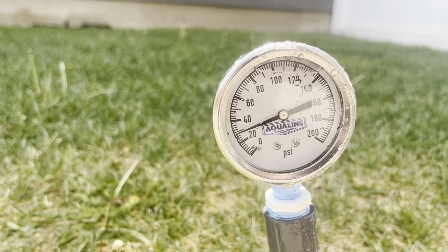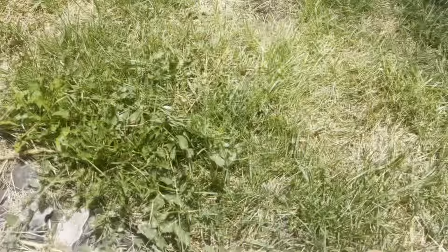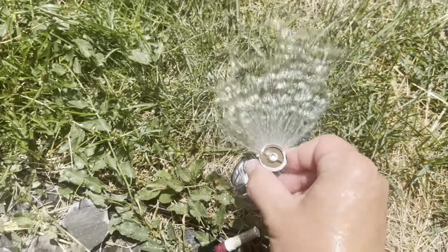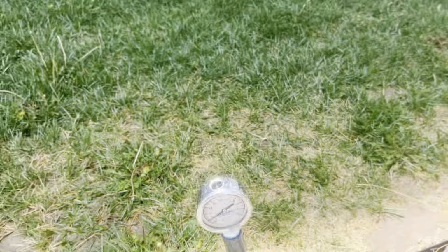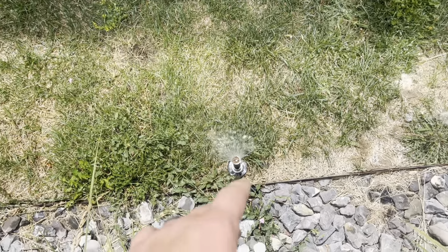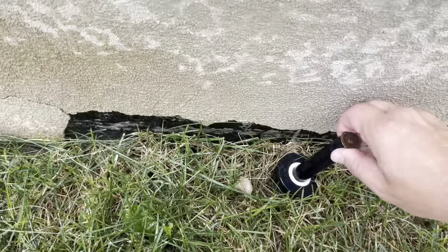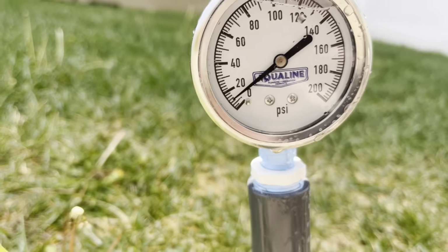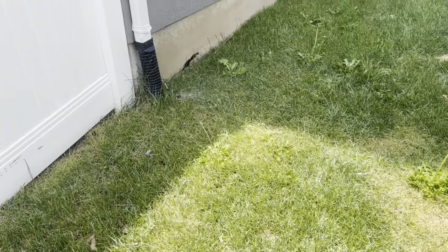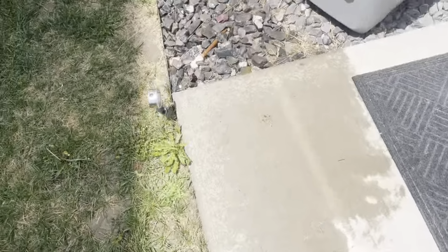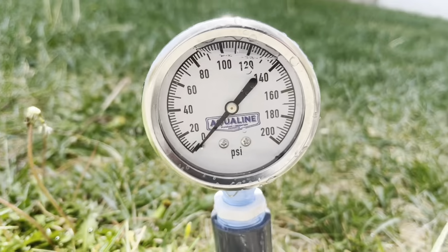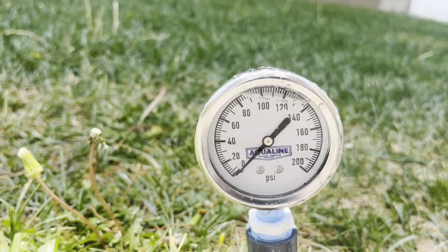That one only took us down by maybe 12, and we're up to like 28, 29. Let's go over and do this guy as well, and I'll open it so that it's not actually hitting me at the pressure gauge, but keep it at close to 180. Now our dynamic pressure has settled down closer to 19. We need to have about 20 PSI of dynamic pressure for these to operate correctly. And open this guy up, and our dynamic pressure now is like 5 PSI. Now you can see they're starting to retract back into the spray bodies. And so if we go over to our PSI, look at that. We have nothing, absolutely nothing.